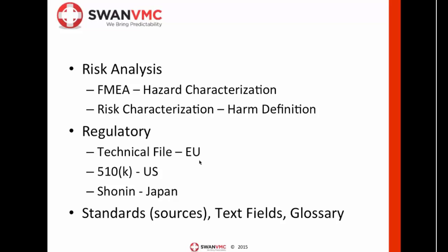And that way, as the engineering departments are doing these failure mode analyses and filling out all these potential risks, what they're actually doing is stacking up the hazardous situations for the risk analysis people to tie to the user harm. And that just makes this whole process of doing risk analysis a whole lot easier.